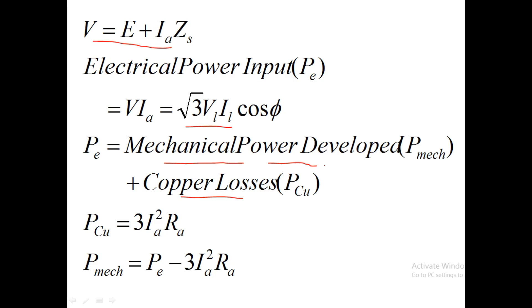In case of every motor, that power which is converted to a torque will be termed as mechanical power. So we can say mechanical power equals electrical input power minus copper losses. Total copper losses is 3 into Ia squared Ra.